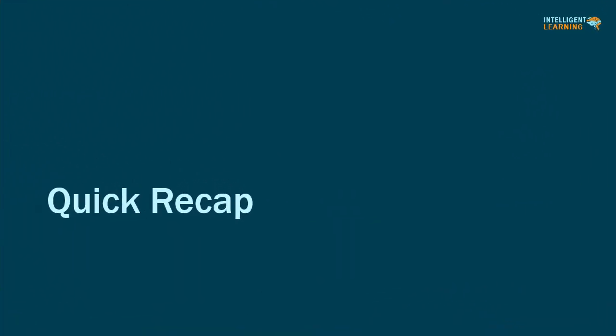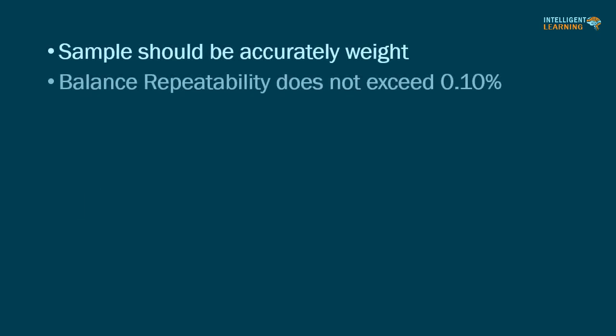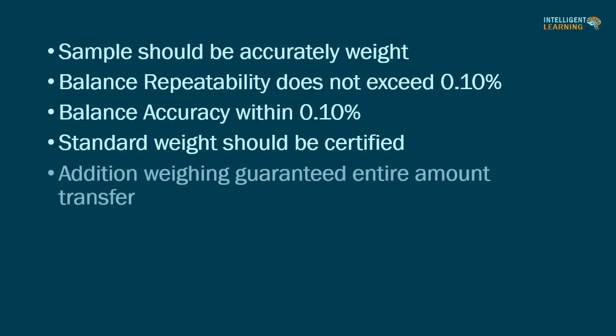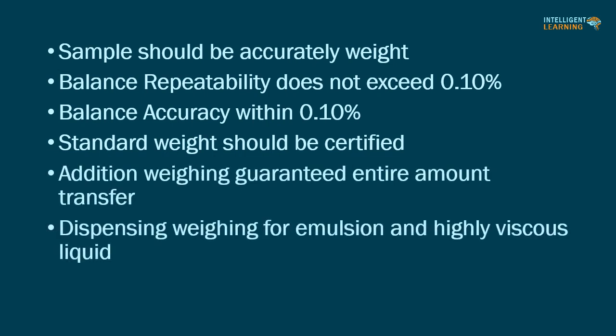Quick recap of this video: samples should be accurately weighed. Balance repeatability must not exceed 0.10%. Balance accuracy should be within 0.10%. Standard weights should be certified. Addition weighing guarantees the entire amount is transferred. Dispensing weighing is used for emulsions and highly viscous liquids.